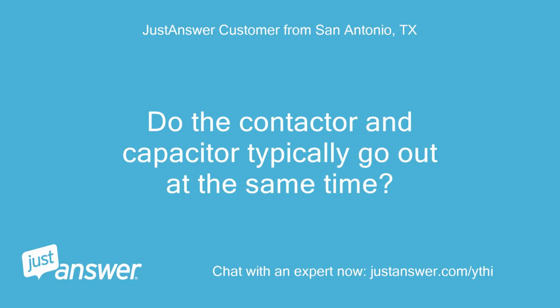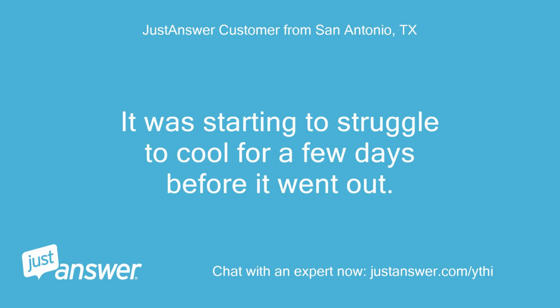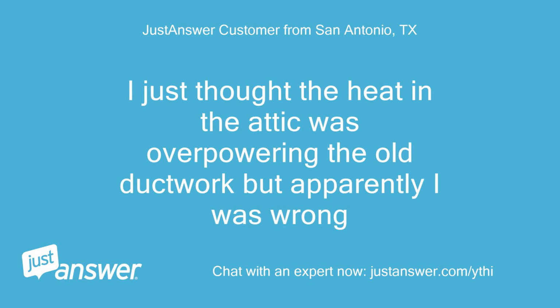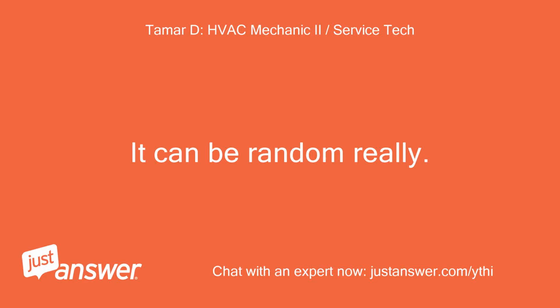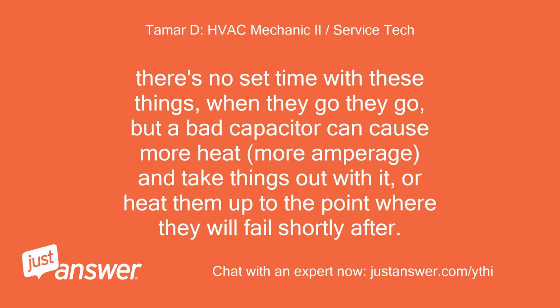Do the contactor and capacitor typically go out at the same time? It was starting to struggle to cool for a few days before it went out. I just thought the heat in the attic was overpowering the old ductwork, but apparently I was wrong. It can be random, really. There's no set time with these things when they go, but a bad capacitor can cause more heat, more amperage, and take things out with it, or heat them up to the point where they will fail shortly after.